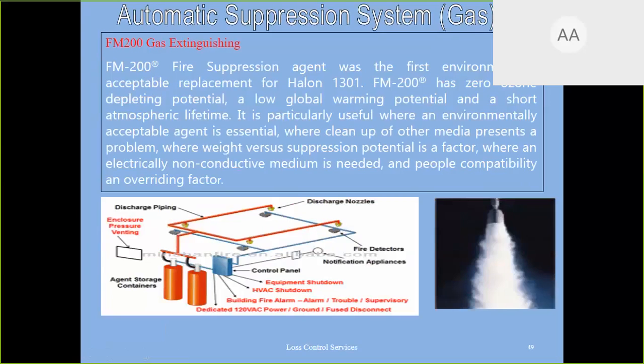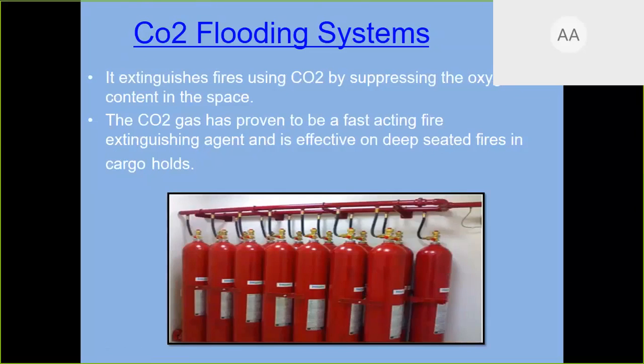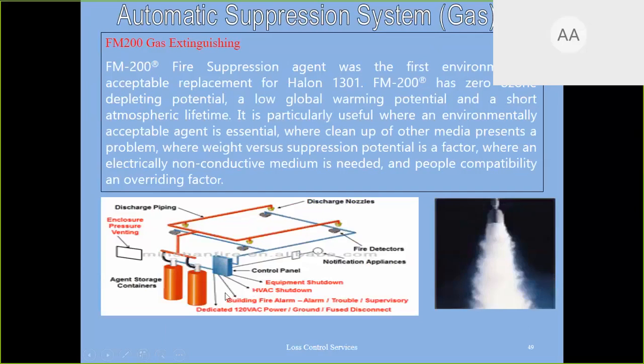So this is something like a CO2 cylinder which is kept. Right? All the cylinders are connected with this header. Right? And this header will go inside the paint shop where we want to control the fire. Cylinders are kept outside the paint shop. How does this work? There is a UV-IR sensor which I told you about in the paint shop. Right? It is installed at each chamber: top coat, base coat, primer, kitchen, everywhere. As soon as the sensor activates, there is a nitrogen cylinder which activates. As soon as the nitrogen cylinder activates, it will activate all the cylinders.